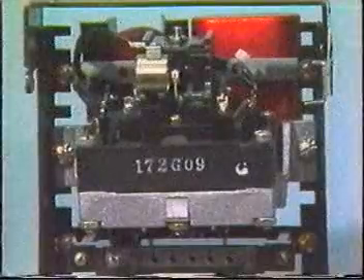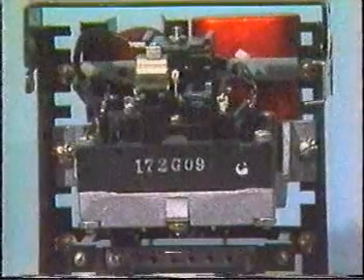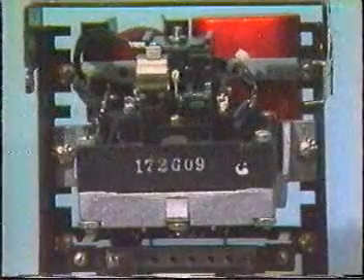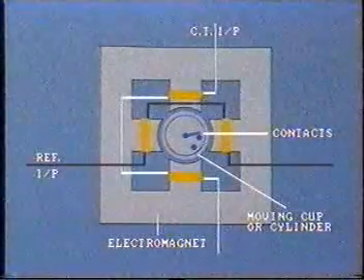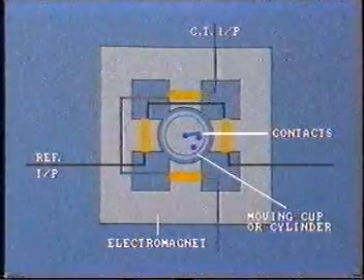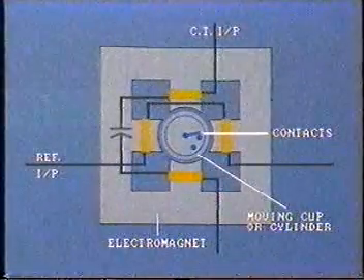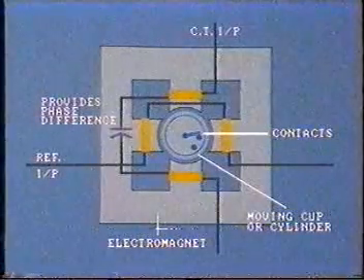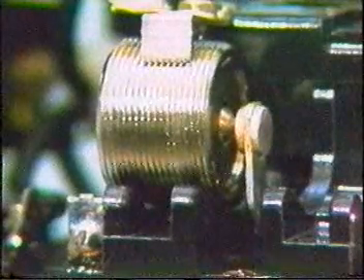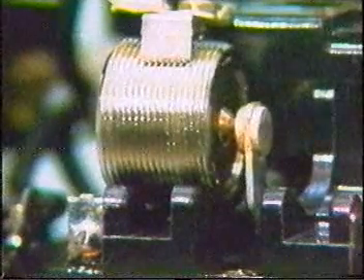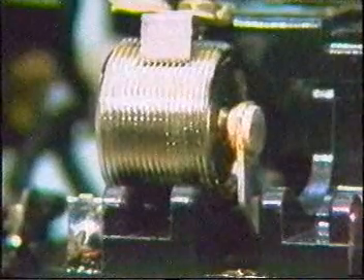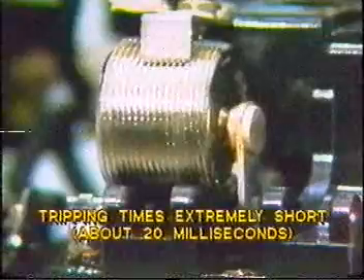In this particular relay, the instantaneous overcurrent element is of a different type — it works on the induction cup principle and is quite similar to the directional unit. The secondary current from the CT is passed through electromagnetic windings. A capacitor is wired into the circuit of one of the coils so as to provide a phase difference between the two fluxes and, in turn, produce turning motion on the cylinder. The spring restrains movement of the cylinder. However, as soon as the current flowing through the coils increases above the set pickup value, the induction cylinder will rotate and close its trip contacts. Only a few millimeters of rotation are required, so tripping times are extremely short — about 20 milliseconds.